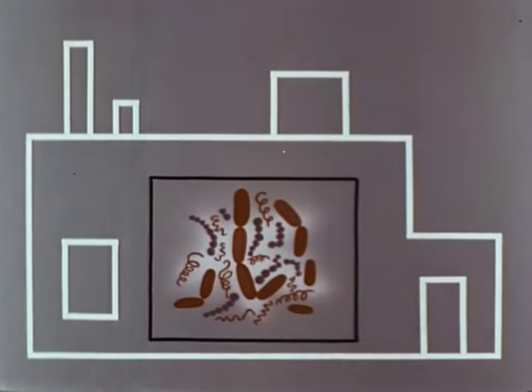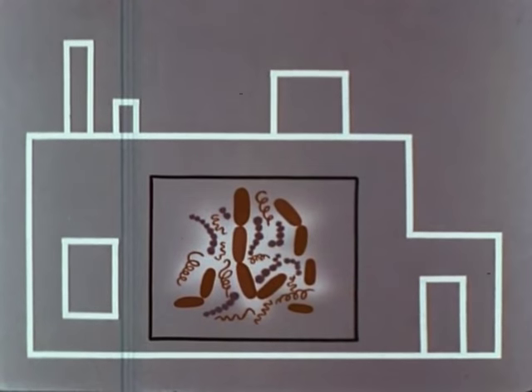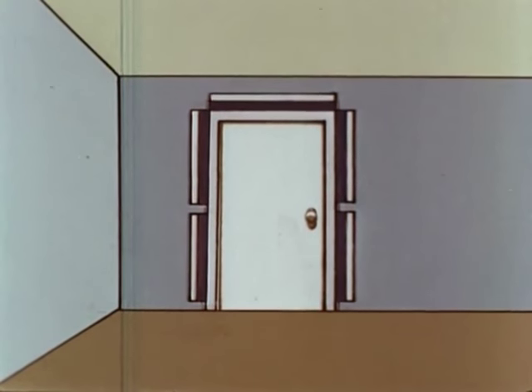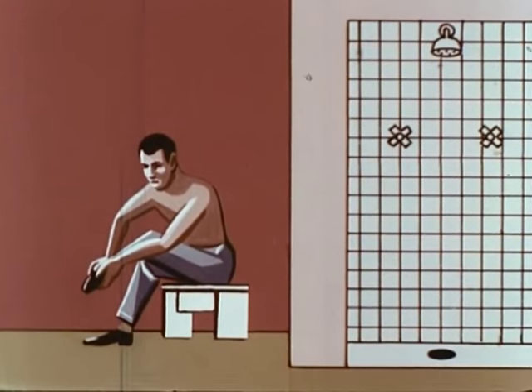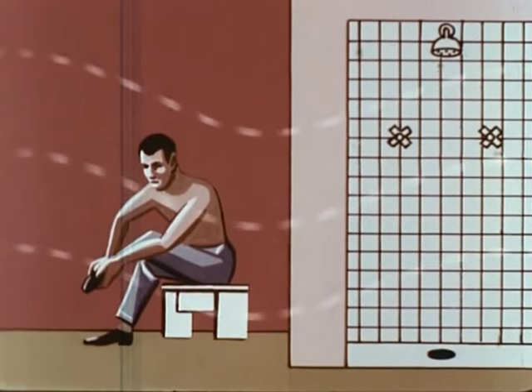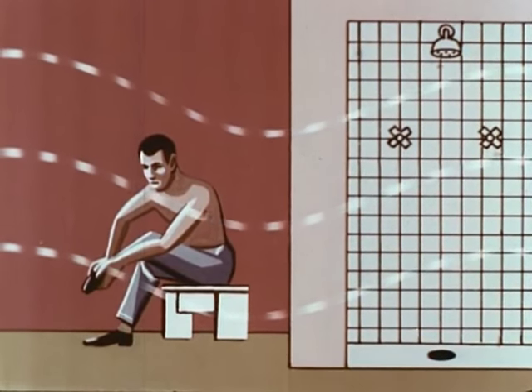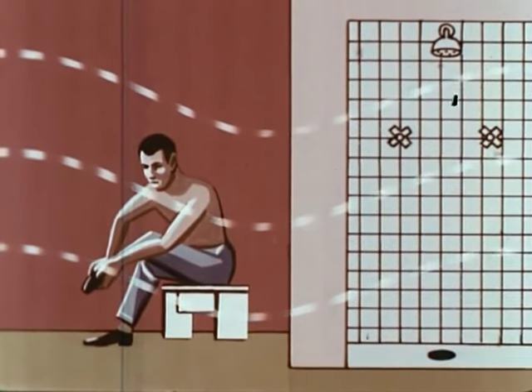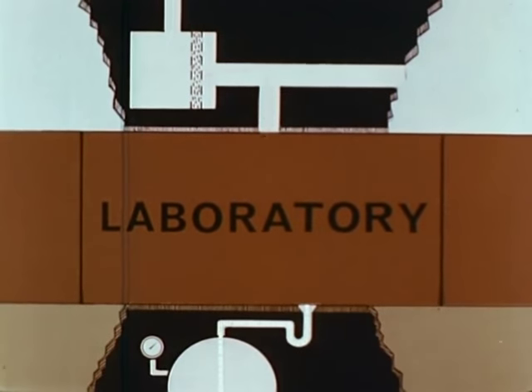The secondary barriers in a laboratory are the features of the building that surround the primary barriers. These provide a separation between infectious areas in the building and the outside community, and between individual infectious areas within the same building. Such features as walls, floors, and ceilings, ultraviolet airlocks and door barriers, and properly arranged personnel change rooms and showers are considered secondary barriers. Increasingly negative air pressure as one moves from a clean area to one of greater infectious risk can also be classified as a secondary barrier. Furthermore, the equipment for filtering air exhausted from laboratory rooms comes under this classification, as well as the facilities for treatment of potentially contaminated liquid wastes.